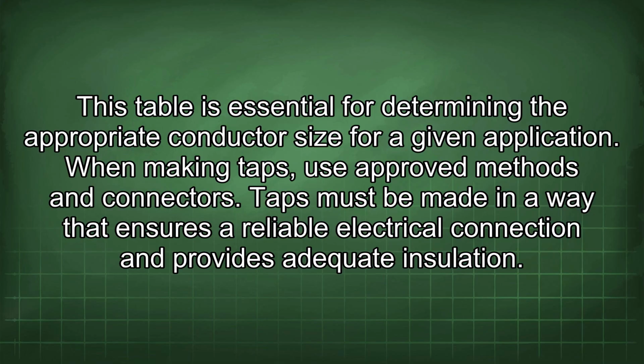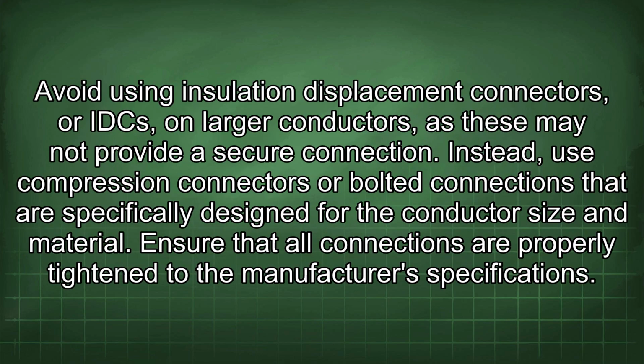This table is essential for determining the appropriate conductor size for a given application. When making taps, use approved methods and connectors. Taps must be made in a way that ensures a reliable electrical connection and provides adequate insulation. Avoid using insulation displacement connectors, or IDCs, on larger conductors, as these may not provide a secure connection. Instead, use compression connectors or bolted connections that are specifically designed for the conductor size and material. Ensure that all connections are properly tightened to the manufacturer's specifications.